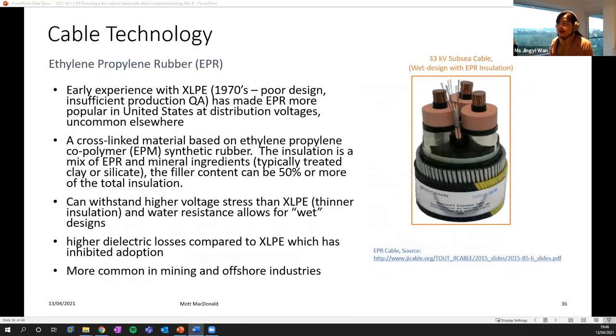And a bit more detail about ethylene propylene rubber, known as EPR insulation. The early experience with XLPE, around the 1970s, had quite poor design and insufficient production quality assurance. EPR was more popular in the US at distribution voltage, and it is rather uncommon elsewhere. EPR can withstand higher voltage stress than XLPE, therefore allowing for a thinner insulation design, and its water resistance also allows for wet designs. However, EPR has higher dielectric losses compared with XLPE, and that is why it is not used for voltage levels above 150 kV.